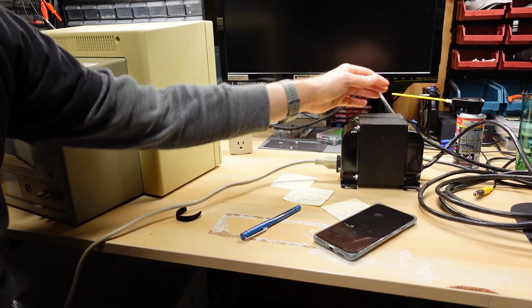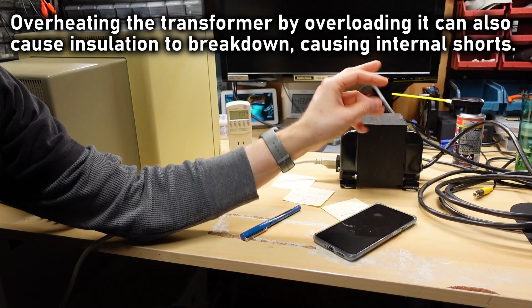Running a transformer beyond its rated capacity, going over 300 VA, isn't going to just stop working - it'll continue to work. I don't think there's a fuse on here, doesn't seem like there's one. But it starts to saturate and the waveform gets distorted, which isn't ideal. You want to try to stay within the rating of a device like this.